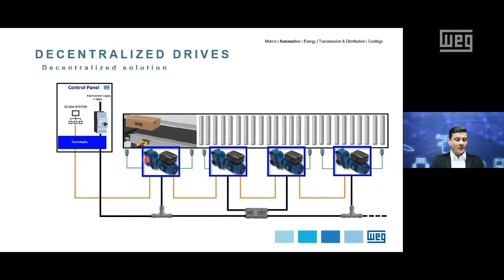And here it's important to highlight that since the VSD is mounted directly to the motor terminals, there is no need to use expensive shielded cables, which results again in savings. And as you can see for this concept of installation, all the digital and analog signals can be read directly at the inverter. Then this data can be transferred over a bus system to the main controller. And of course, due to this concept, the control cabinet can now be made smaller. And for some applications, it's also possible to remove it altogether, which again turns into potential savings for the customer.